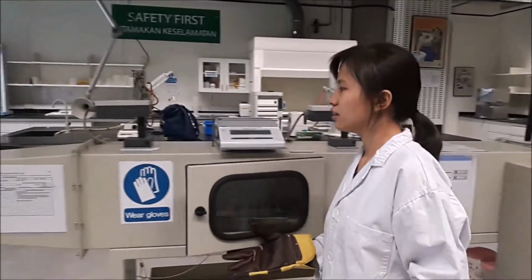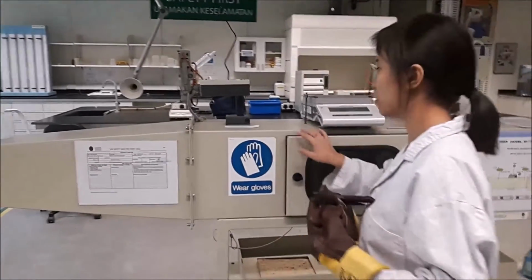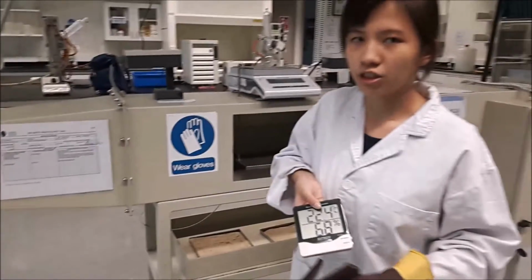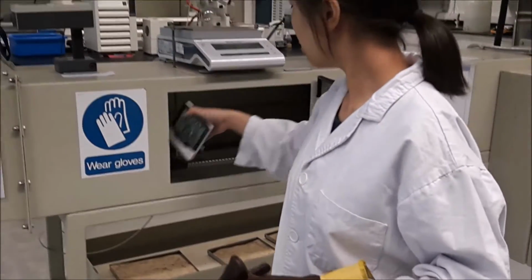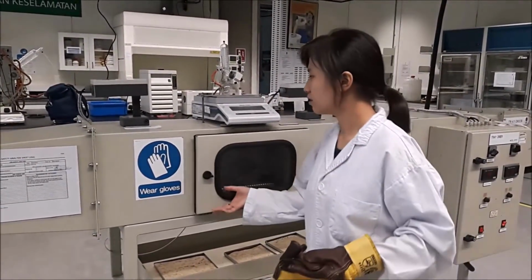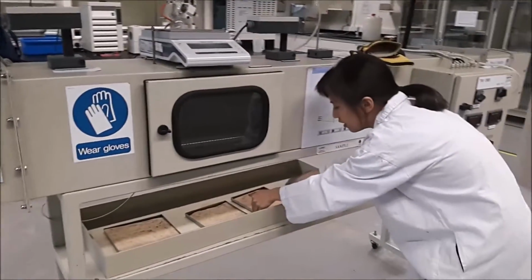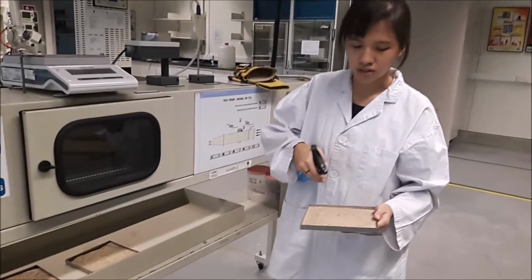Third is the faultiness of the sensor. Due to this faultiness, an external device is being used to measure the outlet humidity and temperature. Last but not least is the uneven distribution of the sand and also the water distribution.